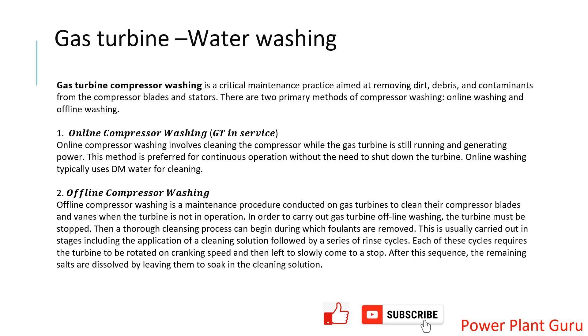You can observe this on your HMI as the compressor discharge pressure (CDP) decreases. In a previous video I demonstrated how to calculate compressor efficiency. Once you start a fresh machine after a shutdown and water washing, calculate the efficiency and then compare it after one month or three months to see the degradation.